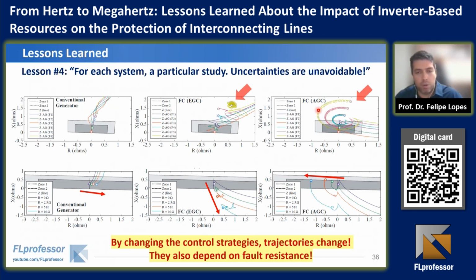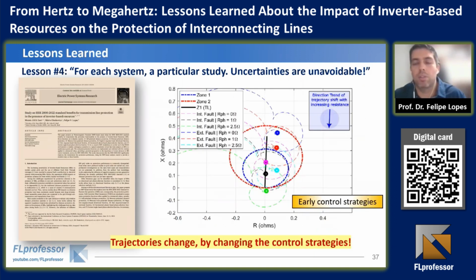And another aspect is related to the fault resistance, because what we expect is to see that as the fault resistance gets higher, the loop impedance moves toward the right side. But depending on these control strategies, they can move down or toward the left side. So by changing the control strategies, trajectories change, and they also depend on fault resistance, so it is a combined effect. And these trajectories are addressed in a recent paper that we published. I have already mentioned it.